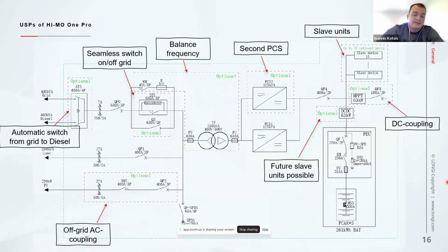Here it's the single diagram, let's say, for this solution. If you want to have a better understanding, of course, we can share this also later. Here we can see, let's say, from right to left, the functioning and the optional features that we can add to the system. So here is the battery, let's say the master. Here we can have, if we want, the DC coupling with the MPPT. So the MPPT is 63 kilowatts, and each cabinet, either master or slave, can have one. So we can add, let's say, up to 11 MPPT, let's say 11 strings of PV.